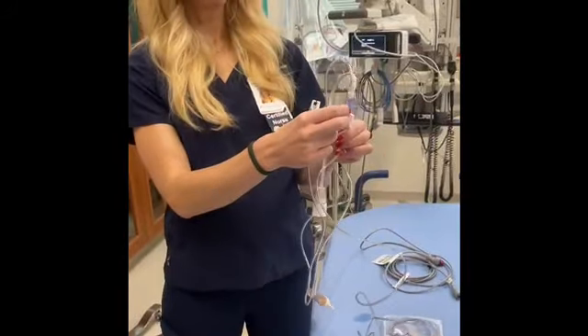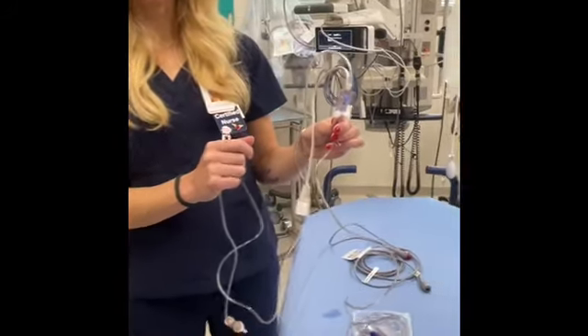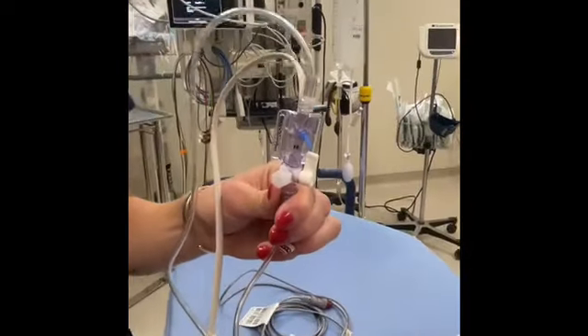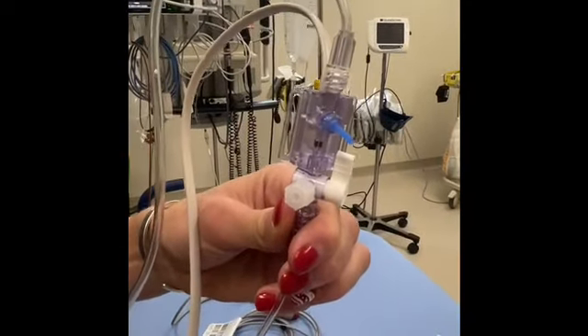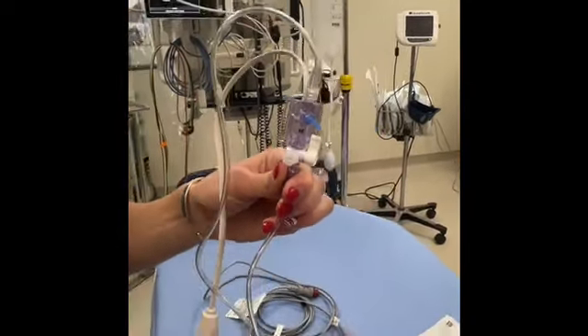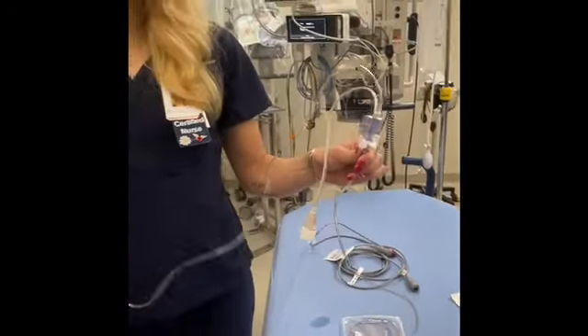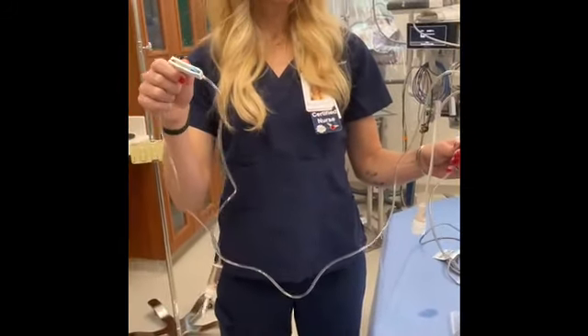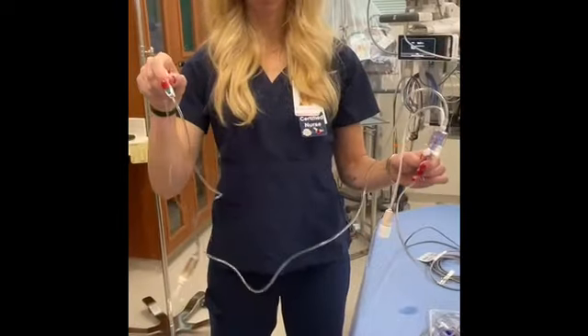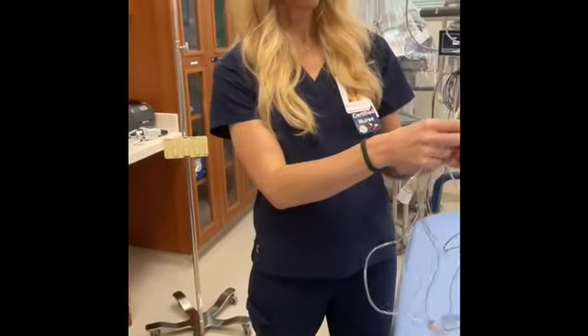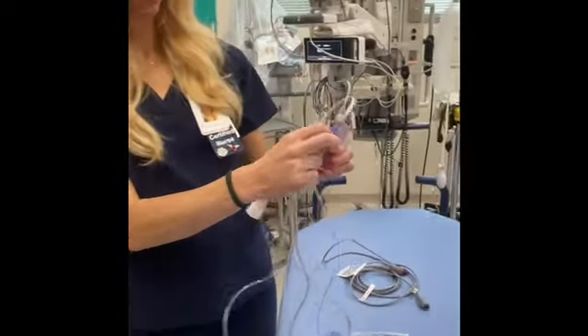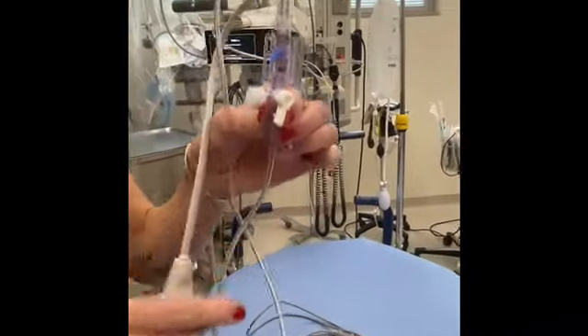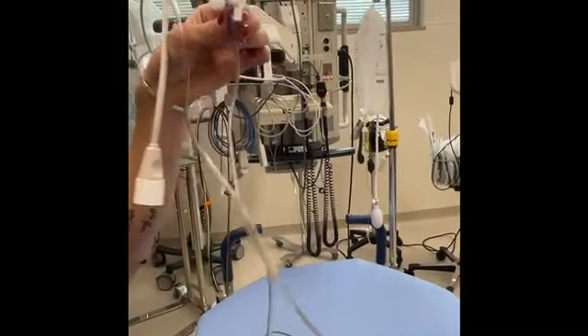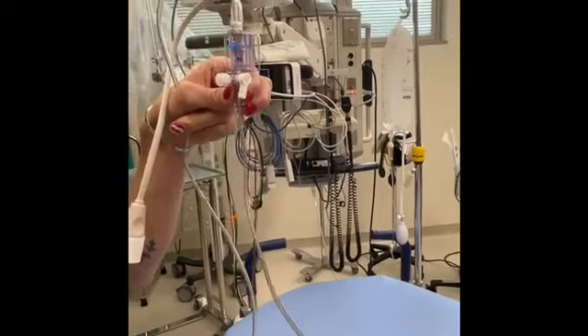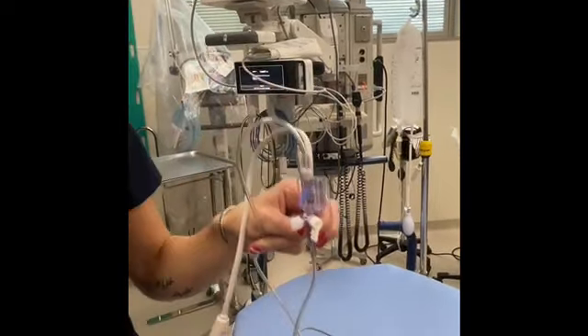Here, this little blue tab is actually called your fast flush device. And in order to start priming the line, we have to get all of the air out of our bag first. So before we attach the tubing to our bag, I like to go ahead and make sure my roller clamp is shut off to the line and that the stopcock here is actually shut off to the patient, because this is the portion of the line that's going to attach to the patient. So we have that there.